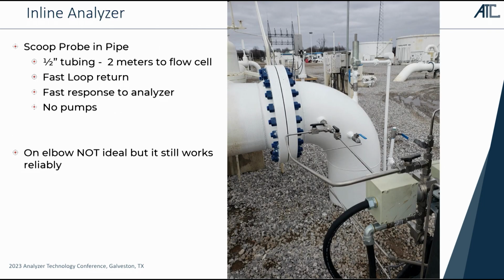Here's one actually, it's not my favorite installation, because these guys put it right in on the elbow of a pipe. But this is an NGL pipeline, and they put the probe into the side of the pipe. They're running a fast loop out, over to a JP3 infrared analyzer, comes straight out of the JP3 infrared analyzer, and goes right back into the pipe. So now they have continuous flow through that flow cell, and it's being driven just by the velocity in the pipeline.